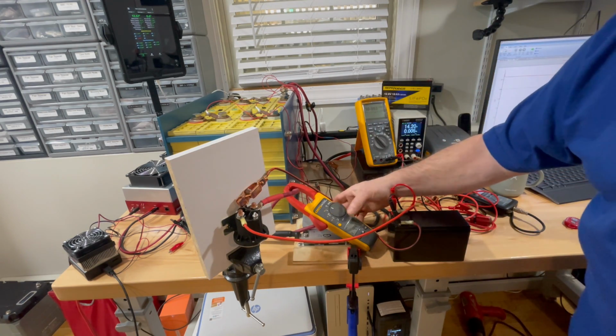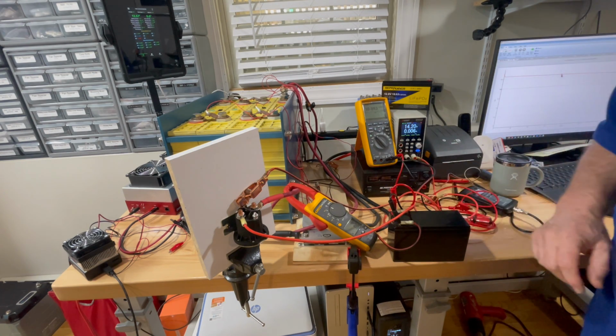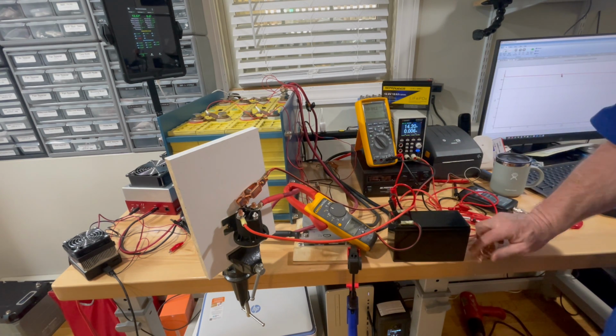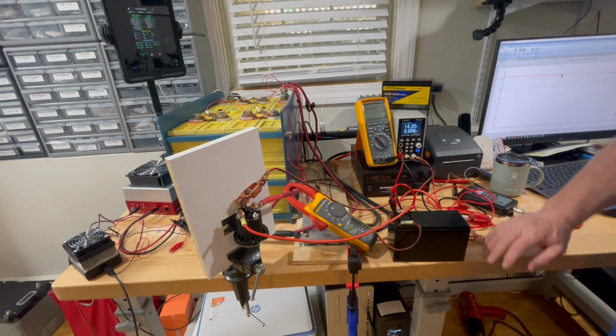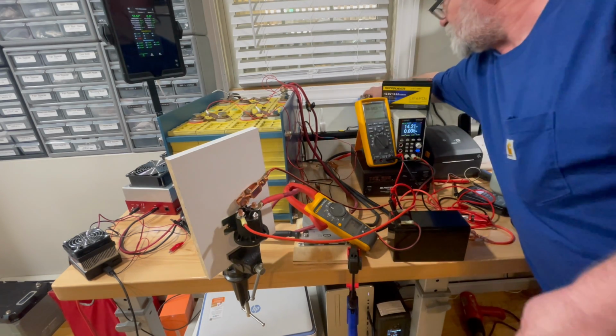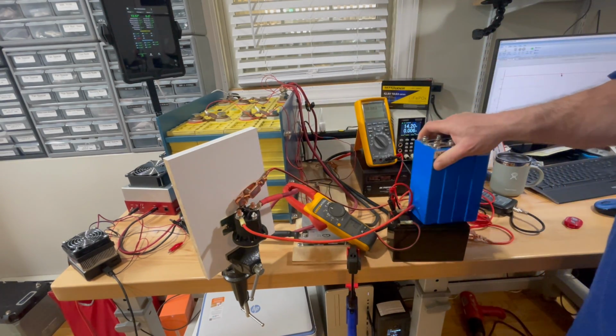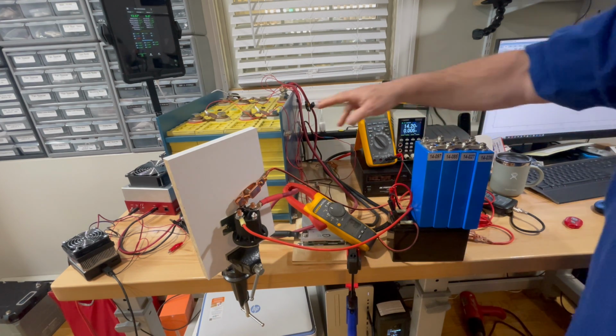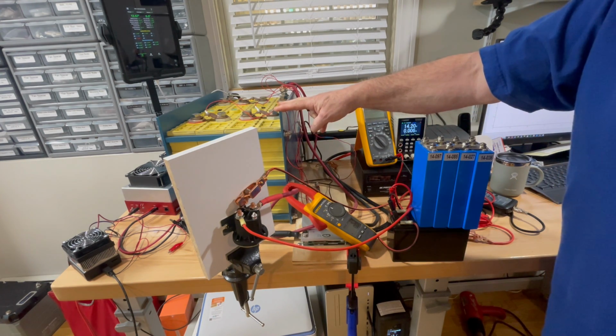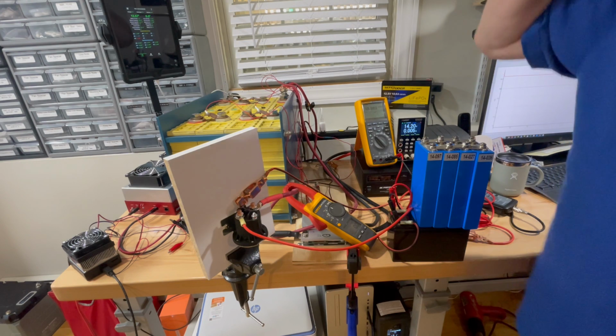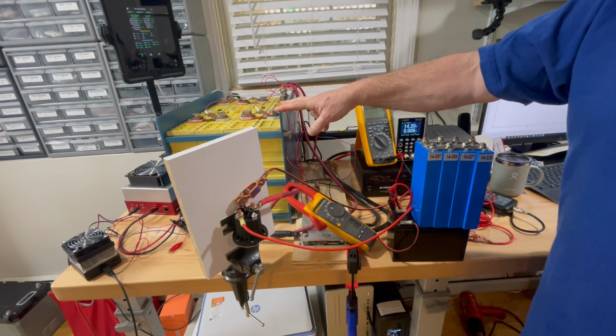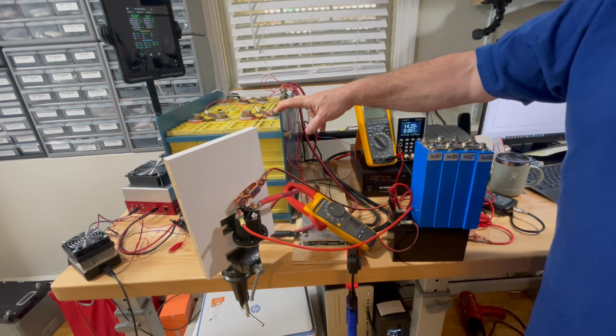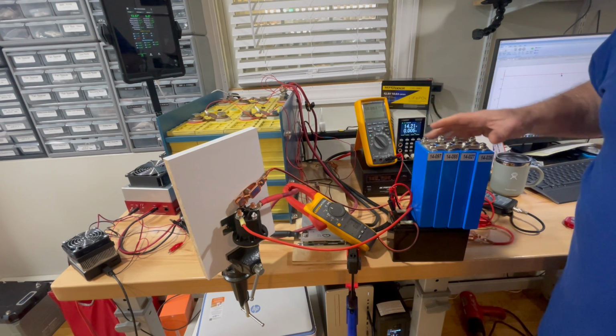So what I'm going to do now is turn off inrush and show you how parity voltage works. The reason I'm showing you this is why the manufacturers tell you to get your batteries at the same voltage before you put them in parallel or series. When you put two batteries in parallel, they don't just balance out. Everybody thinks they do, but they don't. We still have to abide by Ohm's law.